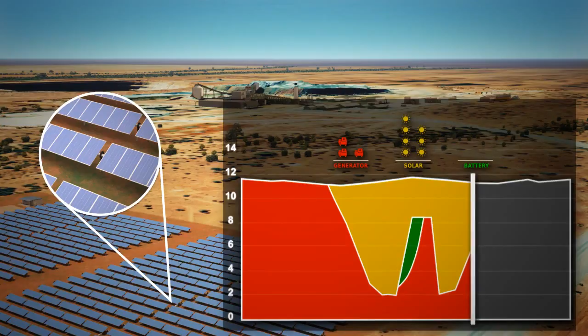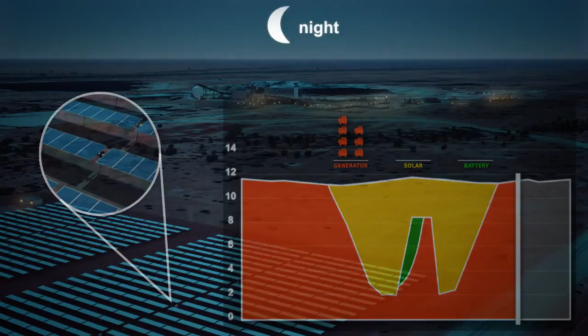As the afternoon approaches and the amount of sunlight reduces, the diesel generators provide a greater proportion of the mine's power needs. During the evening, while the solar power facility itself does not produce any electricity, the battery has the ability to continue providing auxiliary services such as frequency control, power factor correction, as well as a spinning reserve, thereby increasing the overall reliability of the diesel power station.